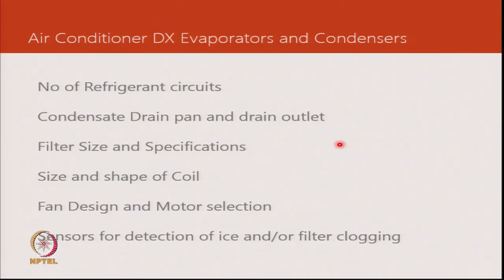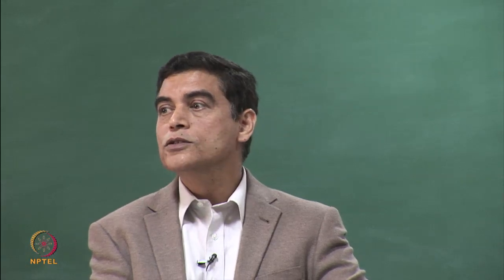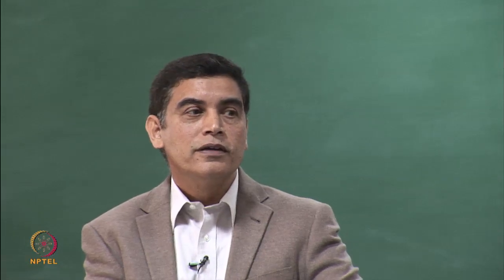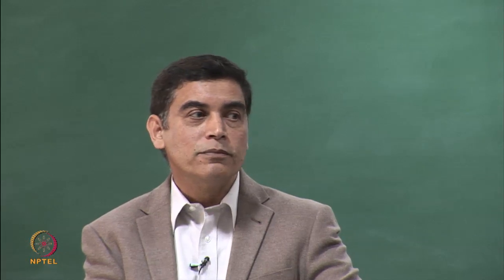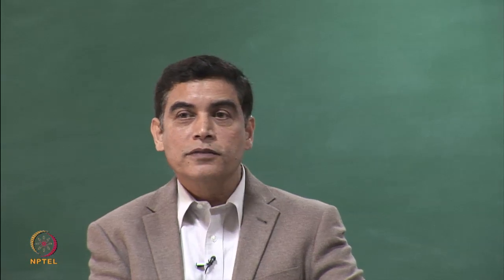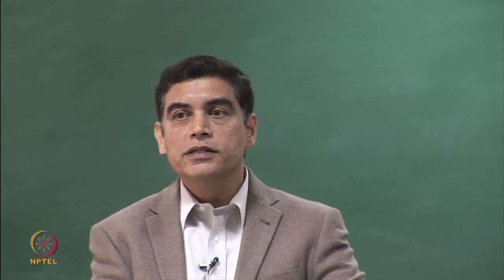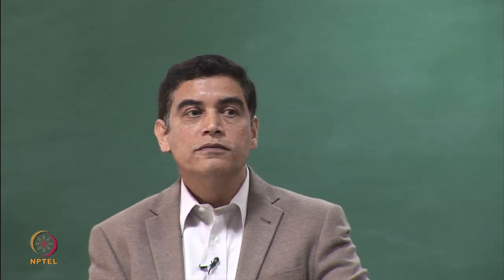In some cases a sensor may be added to protect the compressor or warn the user of abnormal conditions. If a user operates an air conditioner without cleaning the filter, air flow may reduce to perhaps 30% of the design value or even become blocked. While the compressor continues, the evaporator temperature will drop because there is nothing to add heat to the refrigerant, and it could reach freezing temperatures.